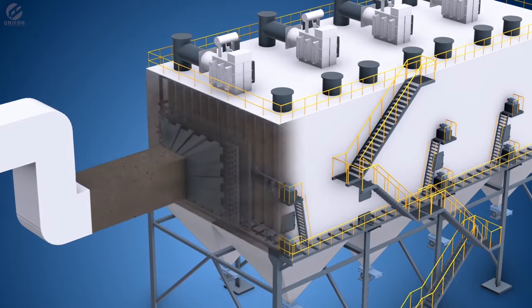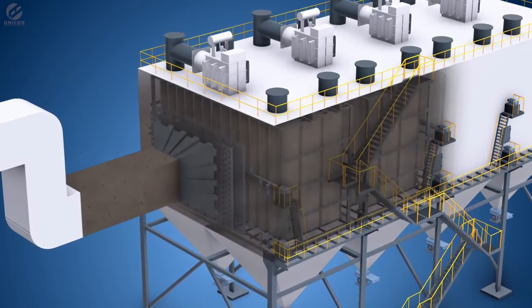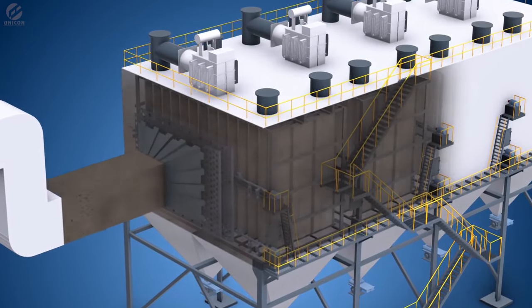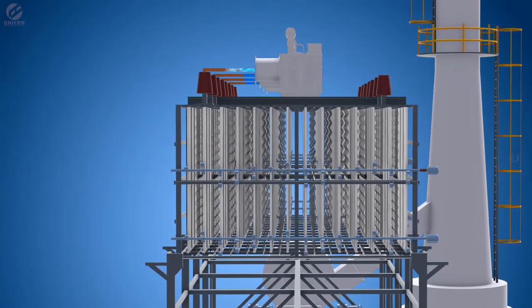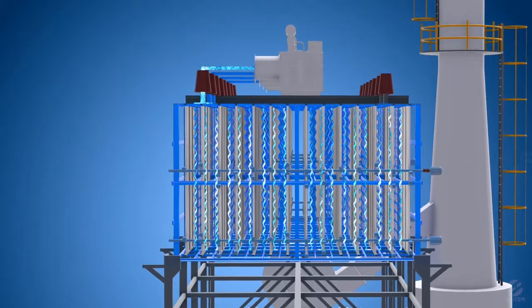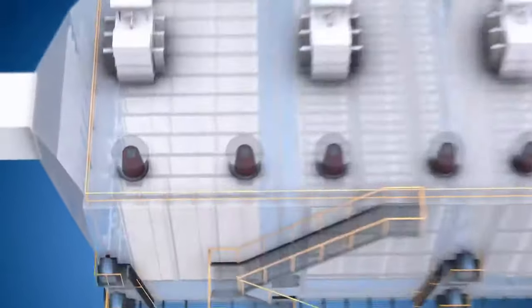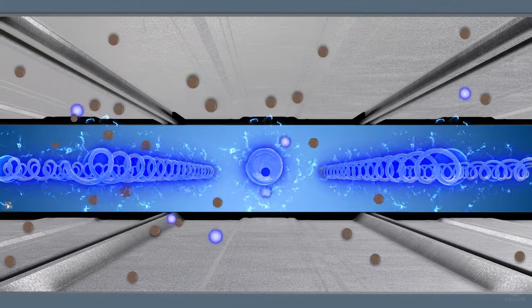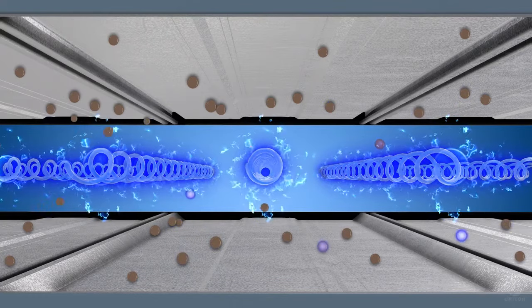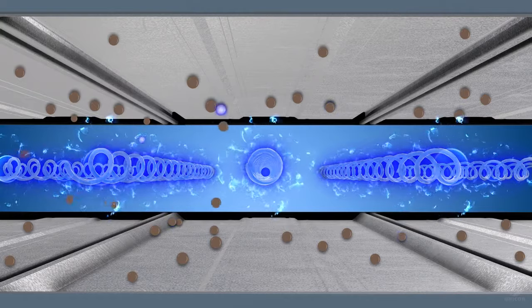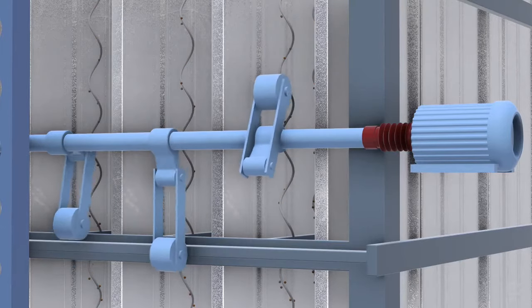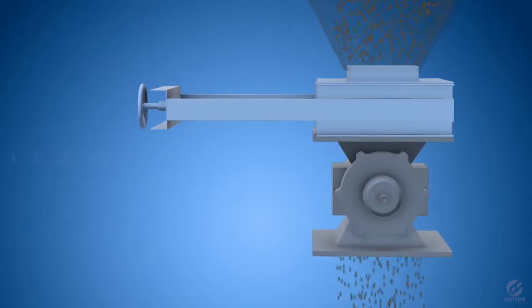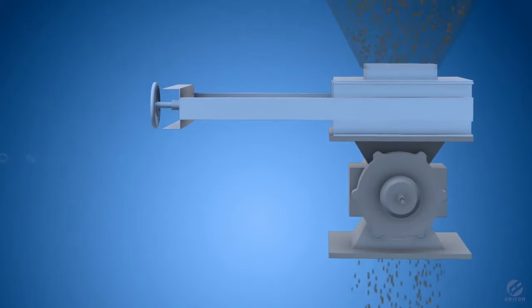The flue gas along with suspended particles enters the ESP through the CFD optimized splitter and GD screen, which evenly distribute the flue gas across the entire ESP. The emitting electrodes in the center of gas flow are maintained at high voltage. The entrained particles are given an electrical charge when they pass through the high voltage electric field. This forces the charged particles to migrate towards the collecting electrodes. The collected particles are then dislodged from the electrodes to the hopper by means of rapping. The hopper is evacuated continuously through the dust handling systems.